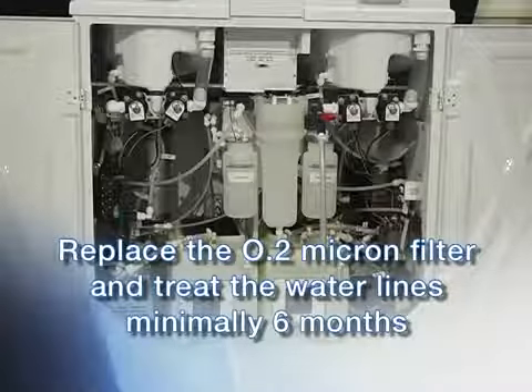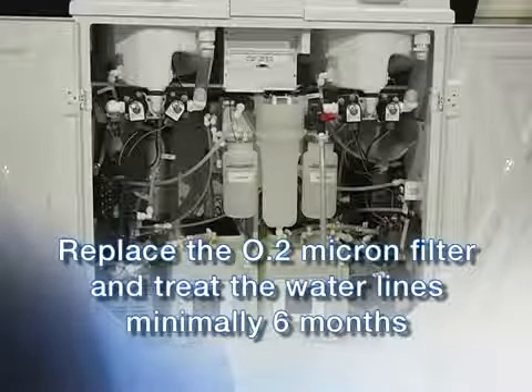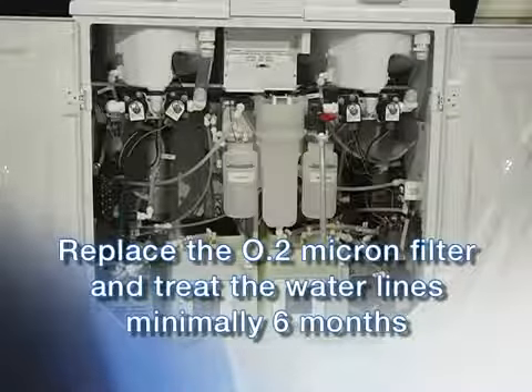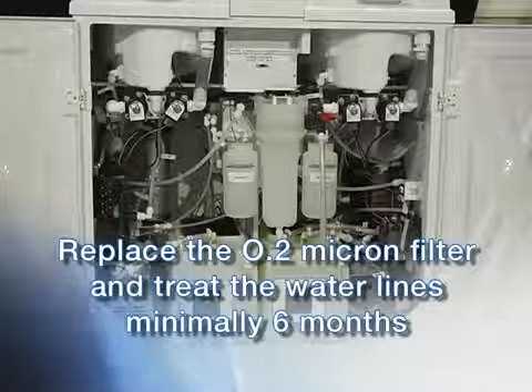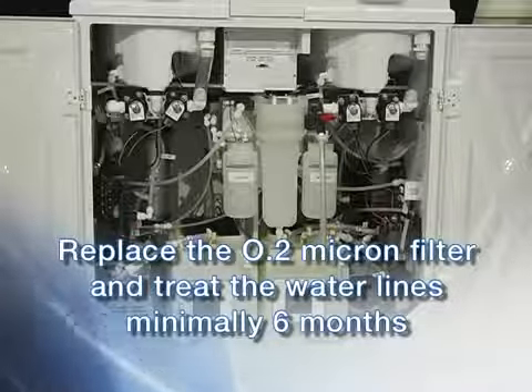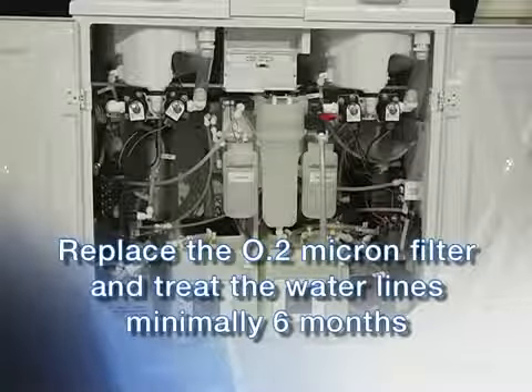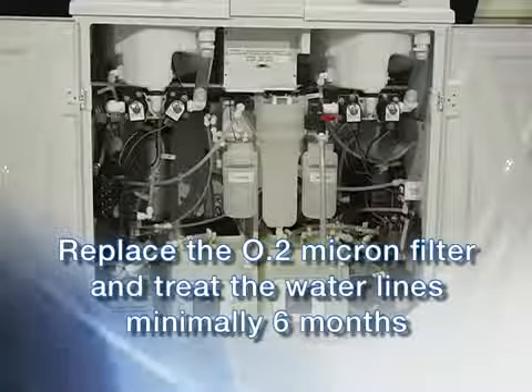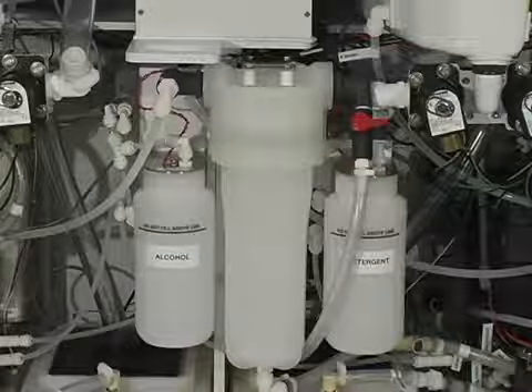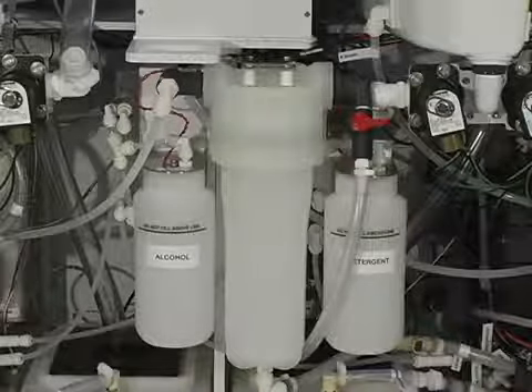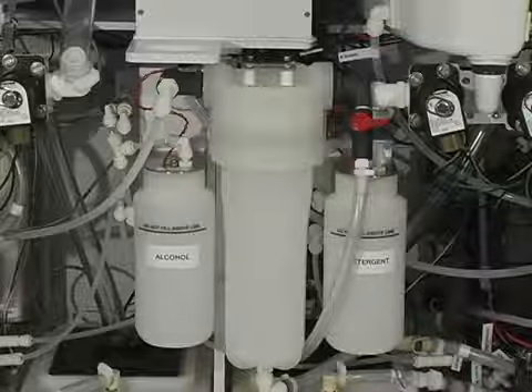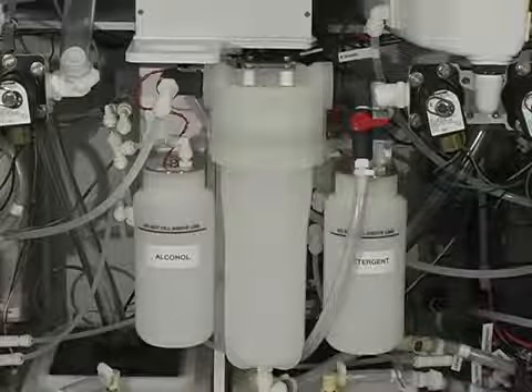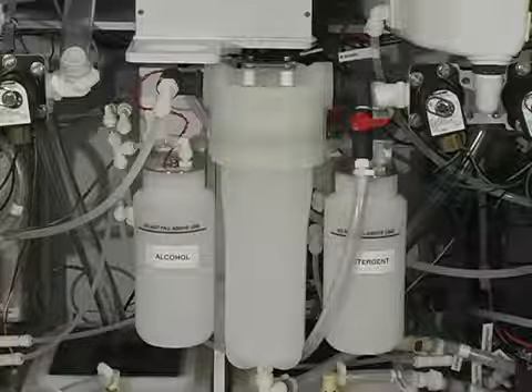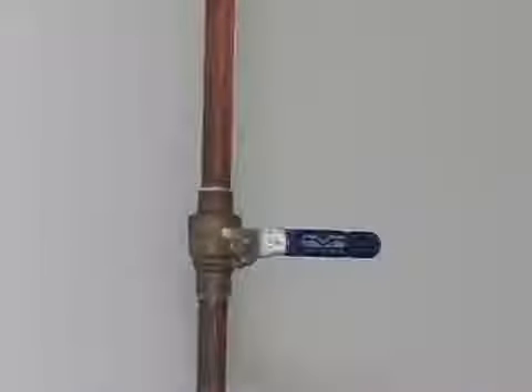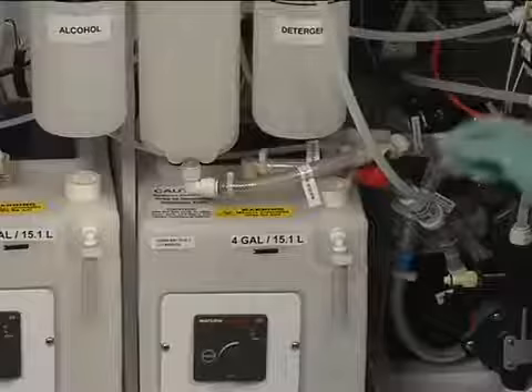The 0.2 micron water filter must be replaced and the water line sanitized at least every 6 months. An important step during replacement is checking for leaks and sanitizing the water lines. Water line treatment includes sanitization of the filter and lines for approximately 1 hour, or for the time programmed for the chemical used for sanitization. The sanitation time is factory set. If you choose to sanitize the water lines for a different contact time, contact technical support or a clinical specialist to make the adjustment. To get started, turn off the incoming water supply and disconnect the water inlet line.